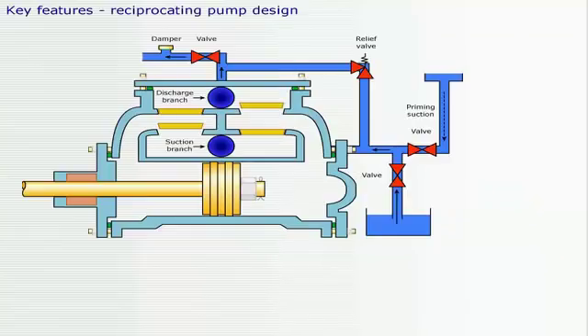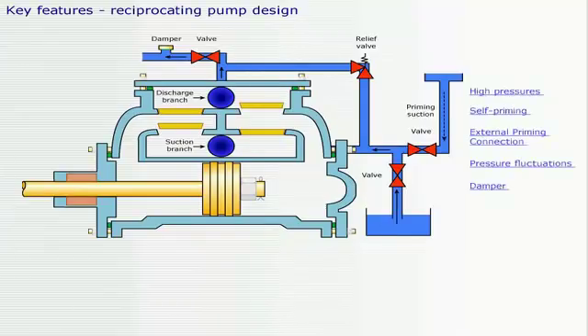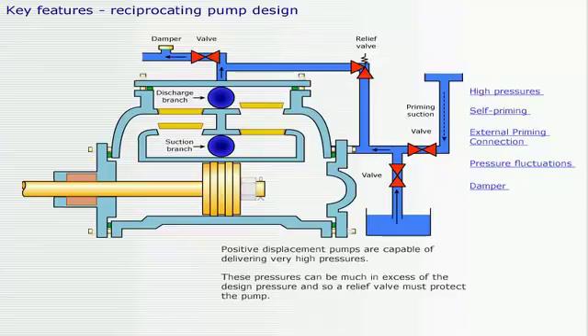Here's an illustration of a reciprocating pump system. Positive displacement pumps are capable of delivering very high pressures. These pressures can be much in excess of the design pressure, and so a relief valve must protect the pump.